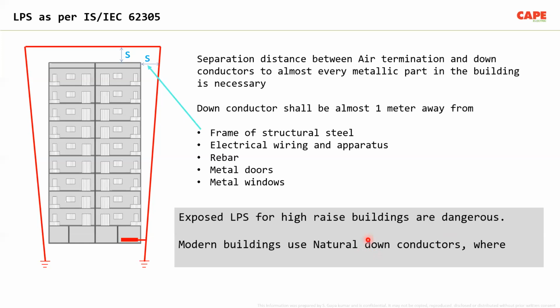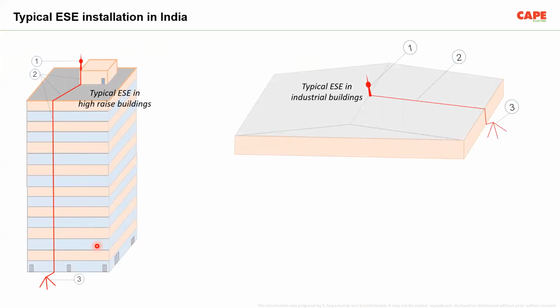And in India, people used to call this an integrated lightning protection system. So for high-rise buildings, you have to have an air termination, down conductors running through the columns or inside the rebar in the columns, and finally the earthing system and equipotential bonding system. This is the correct way of earthing. But unfortunately, 90% of the buildings in India are not conforming to this, and they go for a lightning protection system which is called ESE, early streamer emission.